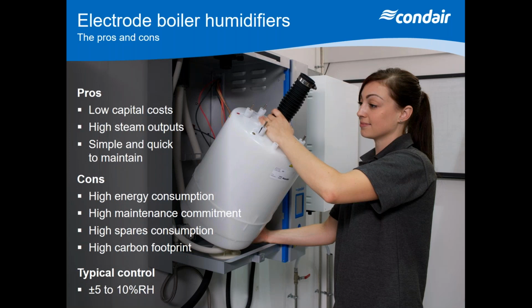But what you're going to find with an electrode boiler is it won't give you the really quick, fast response and close control you need in certain applications like processes. But it's more than enough for commercial buildings where they're looking at a recirculation system, 10% fresh air, and they're perfectly okay. However, if you're working on particularly hard water, you're going to find that they are going to scale up. For example, with London water, you could be looking at maybe 3 or 4 maintenances a year to keep these units in check, certainly if it's 24/7 operation. So it's very vital that you have a suitable regime in place.